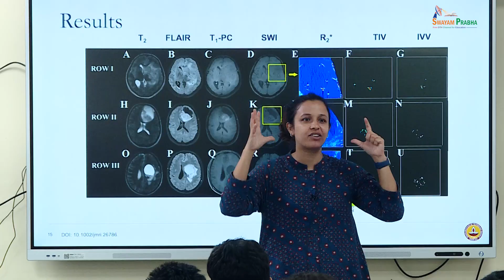Does that also depend on the position of the RF coil? Yes, it depends on the position of the RF coil, which is why when you walk into an MRI scanner, you are not scanning everything. The 2% or 3% who have had an MRI scan might have noticed that for a brain scan, they put a helmet-like structure called a coil on your head. If you are going for an abdomen scan, they will put something on your abdomen. That is the RF coil, telling where the signal needs to come from. So, localization.